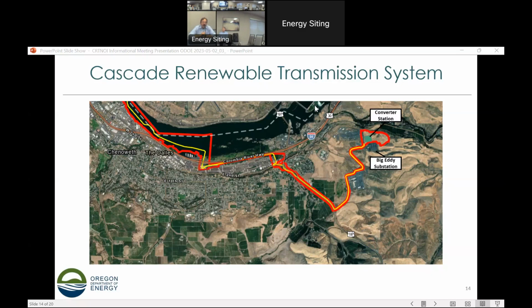It's the serious grounding that goes into terminating the cable where it comes out of the water, and I can only explain it as significant. We've got some photos of transition joints we have in New York, for instance, that we could include to help give folks an understanding of how that shielding goes end to end on the cable surrounding the copper conductor. Yes, the current is increased, but by the same token, the shielding is substantive, and that's an important part of why we can say with confidence that those numbers are pretty low.